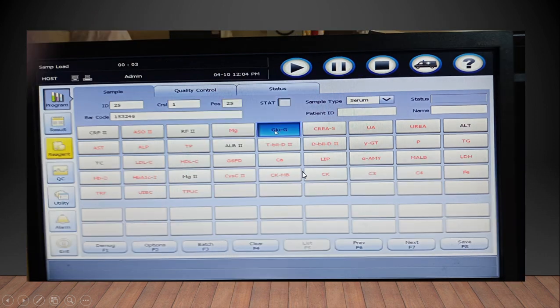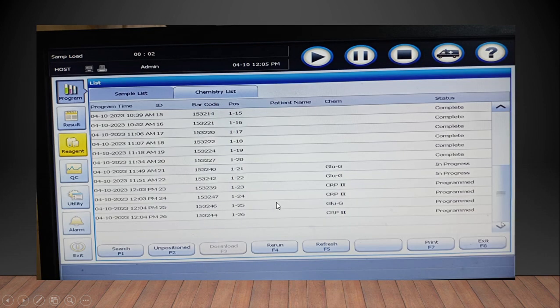The moment you give save, it will immediately go to the next position. Again, for the next position, this ID number is always constant, you should not change it. You enter the barcode, now you have selected the test as glucose, and then you save it again. You can keep on doing like that for whatever tests you need to give to the instrument.